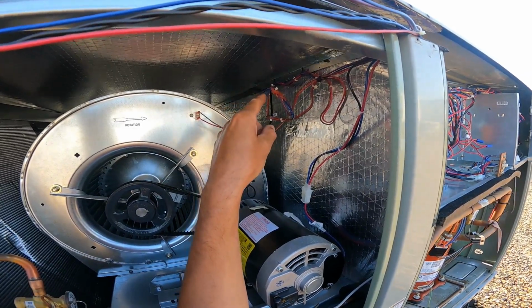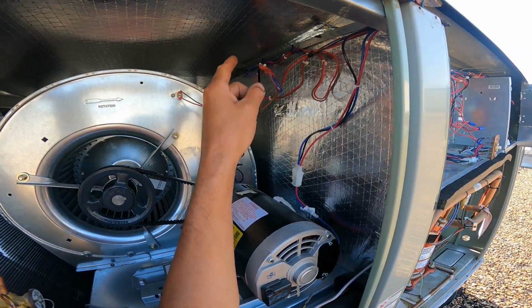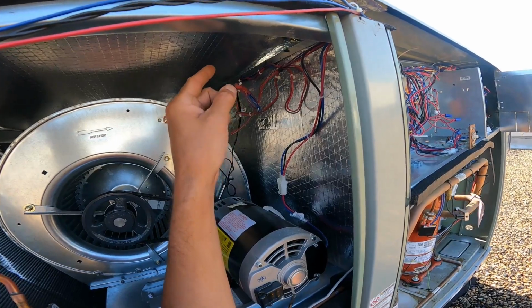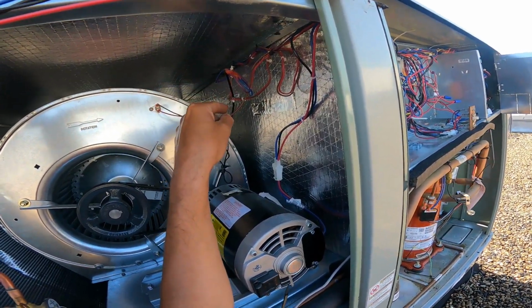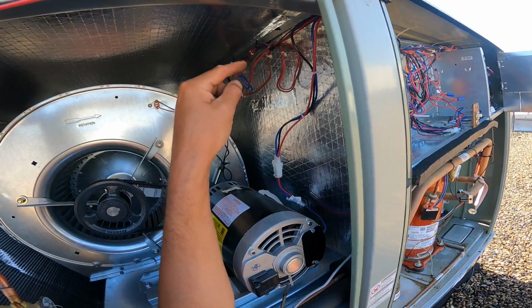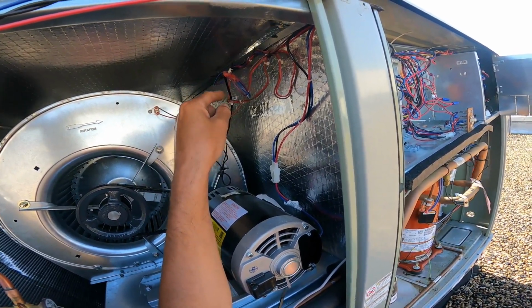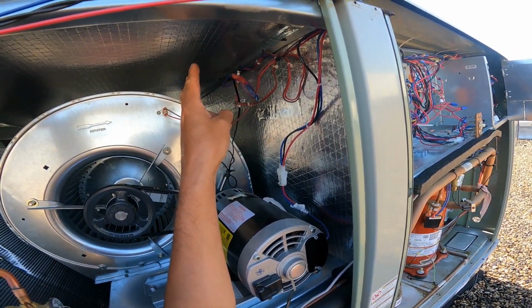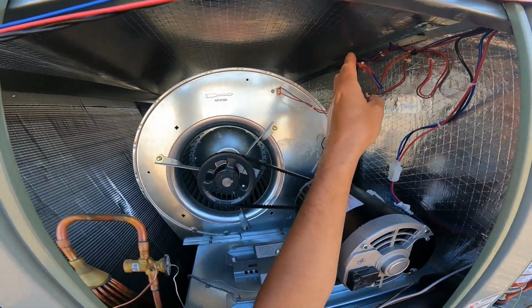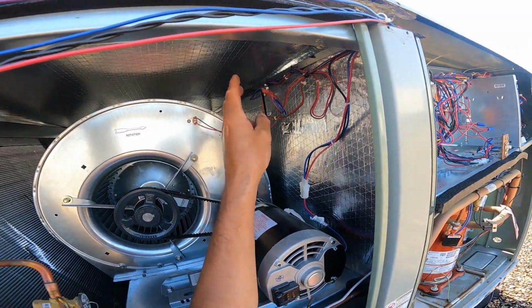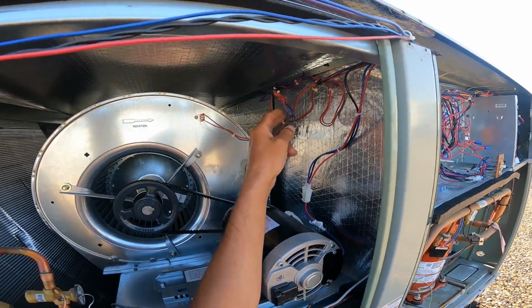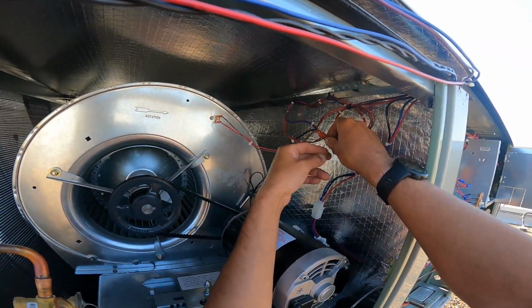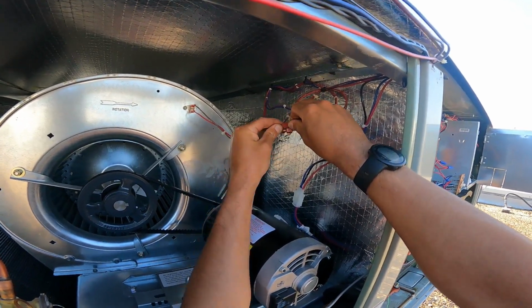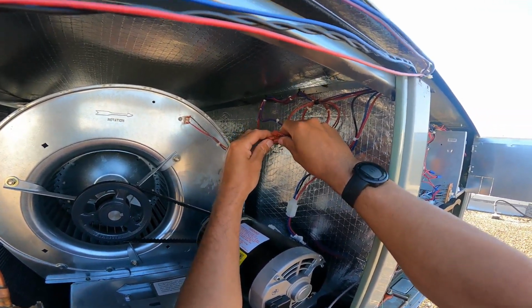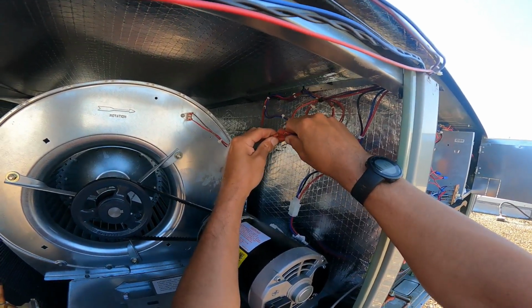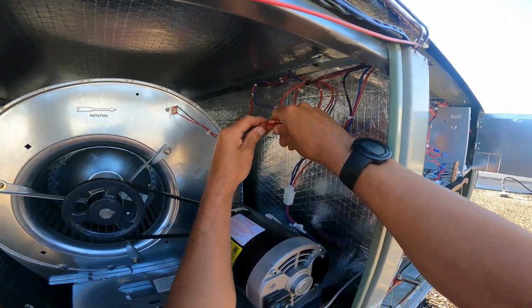But what I don't get, and maybe you know, because I don't, we should not be sending voltage through a sensor. That's not, in my experience, how a sensor is supposed to work. So what I'm going to do is unplug it from here, plug it back into the module, and see if the module trips. If it does, we've got a problem in the wiring. If it doesn't, then we've got a problem with this sensor.